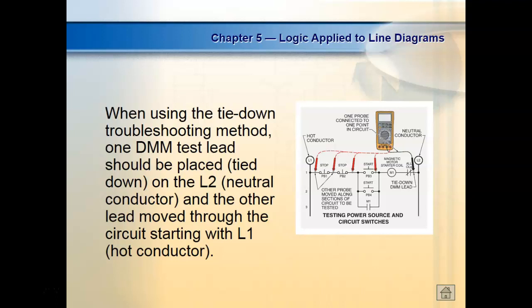We're going to be dealing with 120-volt AC in here, so we've got to play around with some PPE. Most meters come with an alligator clip for both your leads. Normally what we do is snap that on to the L2 side and then move toward L1. You've got to have somebody press the normally open push buttons because it's going to start off with nothing there — somebody's got to push them in. Normally closed contacts are okay, and we troubleshoot from the output toward the input.